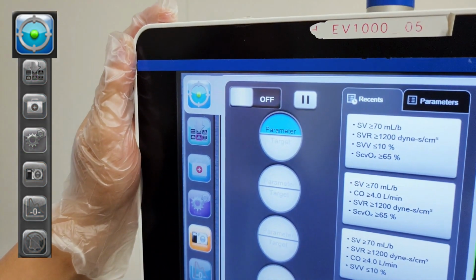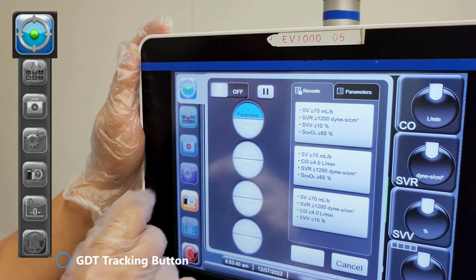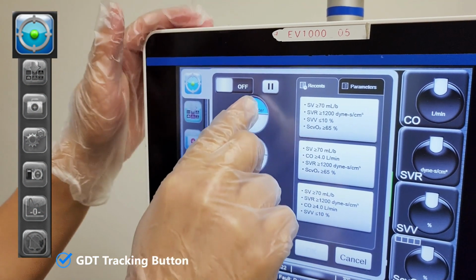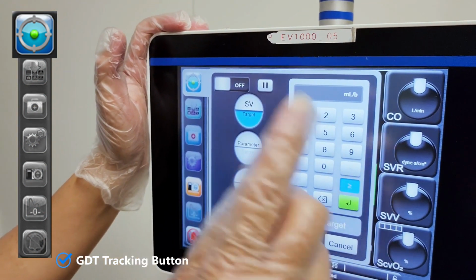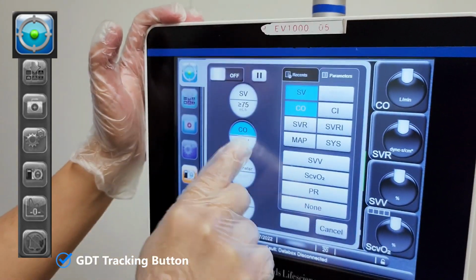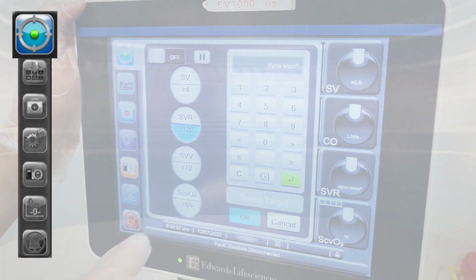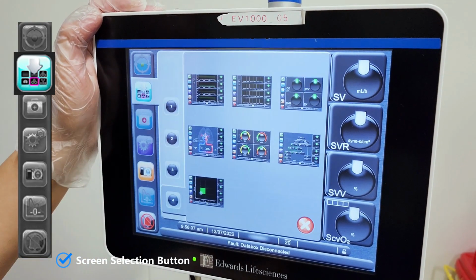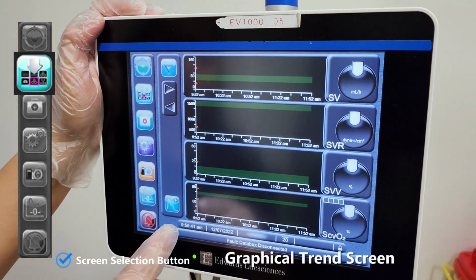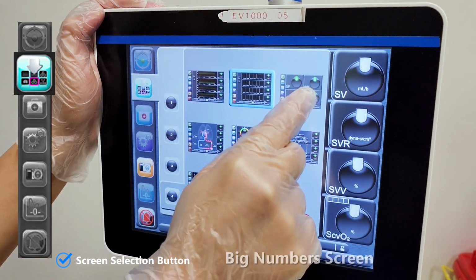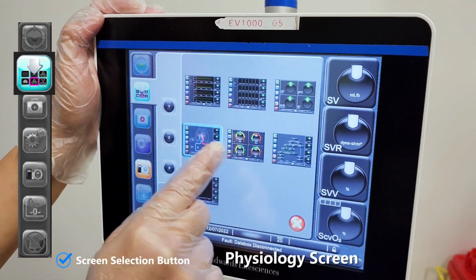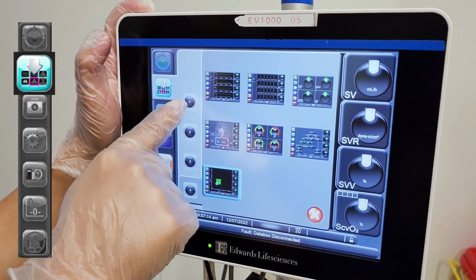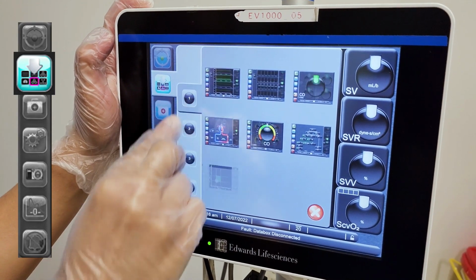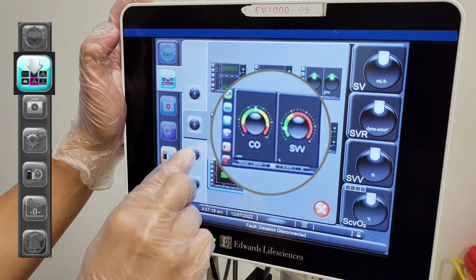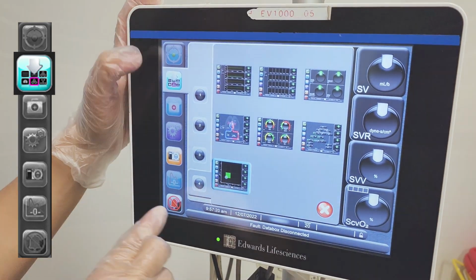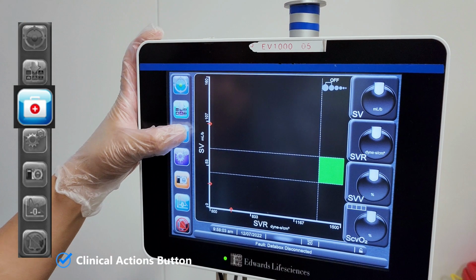From the top, the first button is what we call the goal-directed therapy tracking, or the GDT tracking button. Here, you can set up to 4 key parameters and adjust your target selections. Monitor screen selection button, where you can choose among the 7 monitoring screen formats. So these are your monitoring screen options. The circle numbers 1, 2, 3, and 4 represent the number of the key parameters to be displayed on the monitor. The clinical actions button.